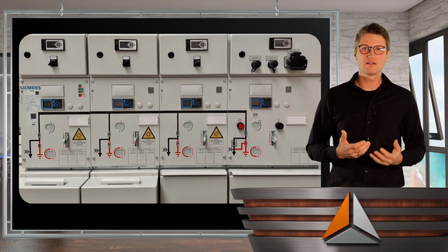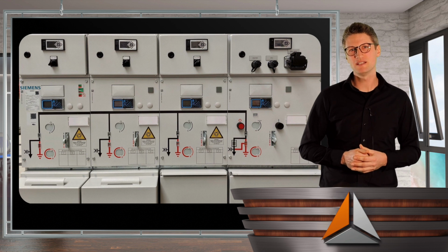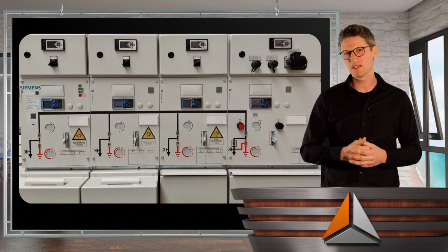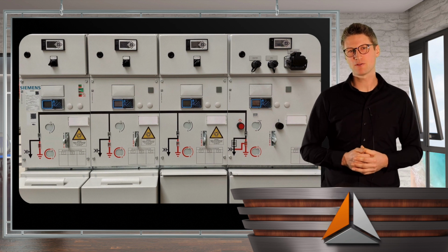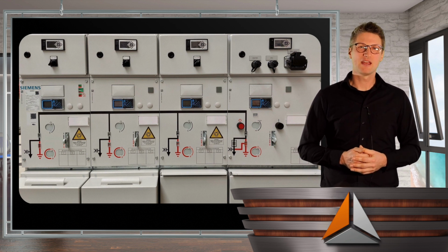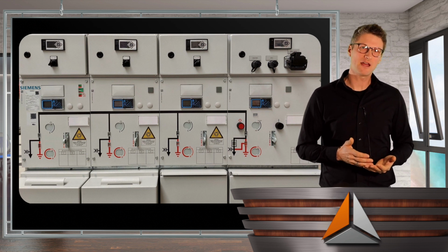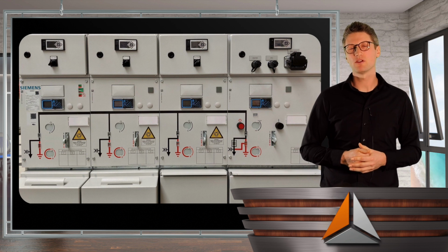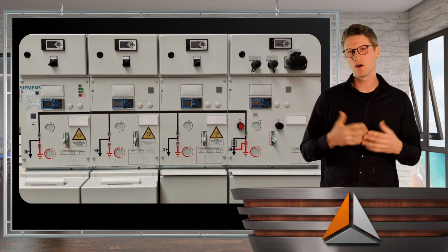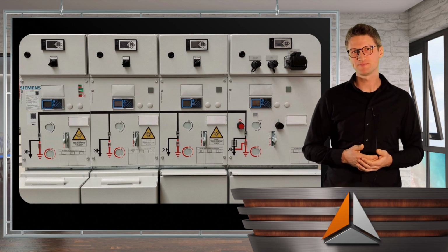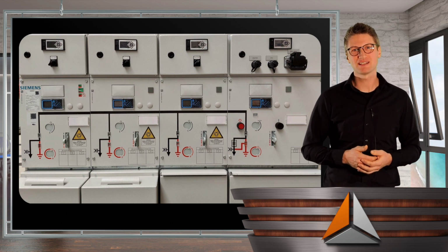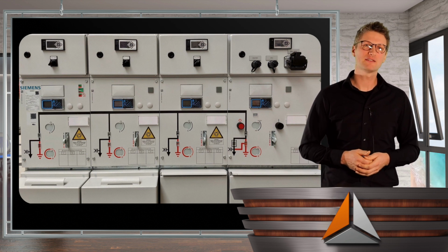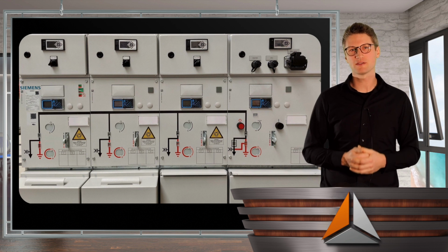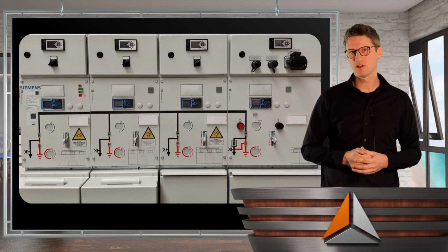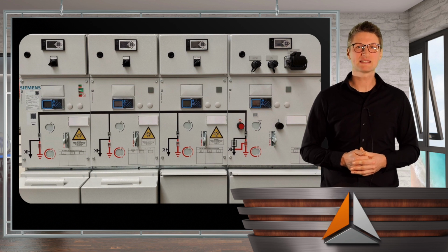Yeah, what are the upcoming pain points of DSOs like Netze BW here in Germany that they see from this background in the medium voltage level? At the moment, compact switchgear stations and secondary substations are often not monitored at all. So the DSO has no measurements in the depths of the network. The grid situation is changing dynamically and several times a day, and therefore also critical situations can occur. And secondary substations are normally not remotely controlled. That means that critical situations cannot be solved quickly.